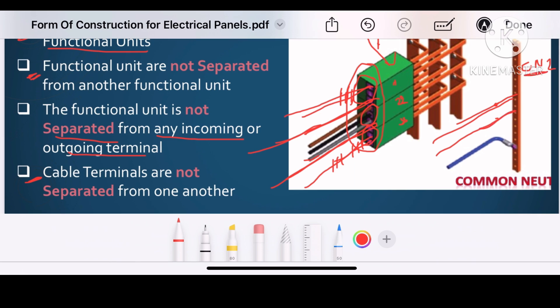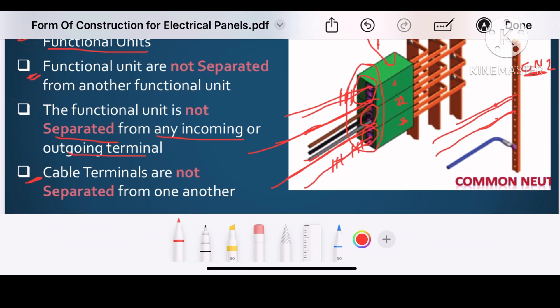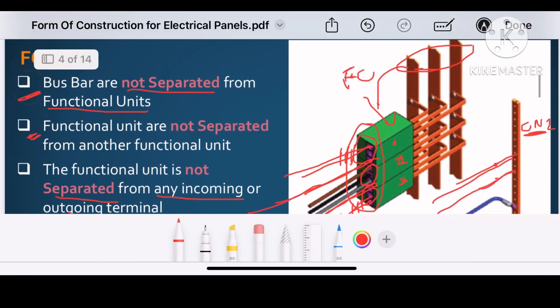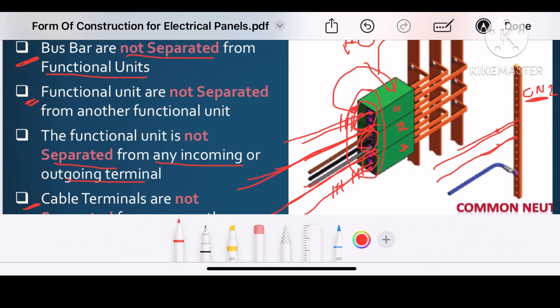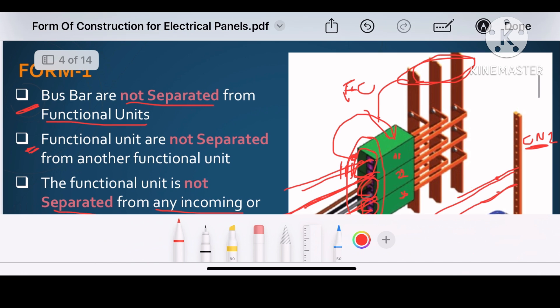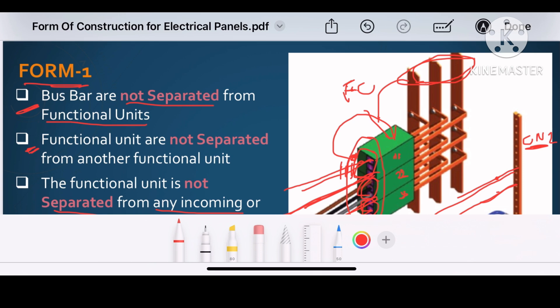In form 1 construction, the cable terminals are also not segregated from each other. For example, the RYB cables connect to each functional unit and the neutral is connected to a common neutral link — there is no separation between terminals. So in form 1 construction, there is no separation in the major components: between bus bar to functional unit, and in the cable terminals.